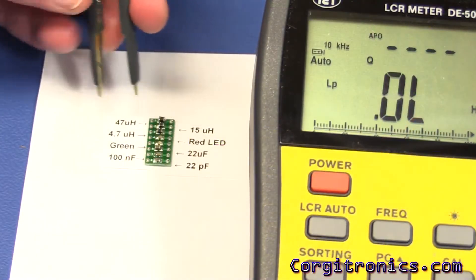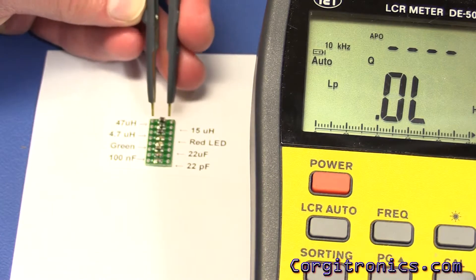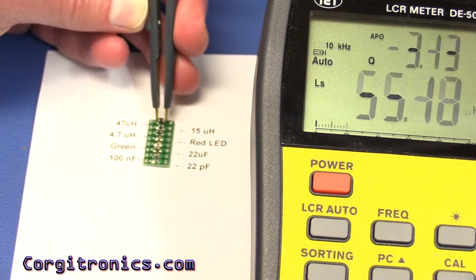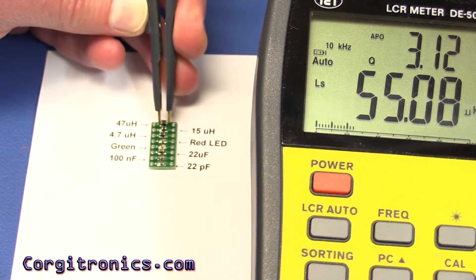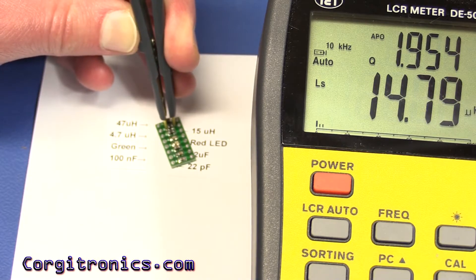Let's run through the inductor values and see what the IET says. On the 47 µH at a test frequency of 10 kHz, we're showing 55 µH and a Q factor of 3.12. On the 15 µH we're showing 14.79 µH with a Q of 1.9.